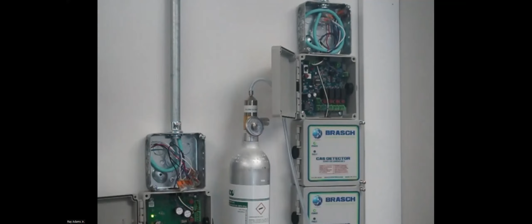And then you simply have to daisy chain that expansion pack right into the sensor that's closest to it on that particular floor. So instead of running your fans from the 5th floor of a parking garage all the way back to a maintenance room where you have your control panel, you take that and mount it right next to it. And as you daisy chain that expansion pack in, there's actually a repeater or a booster built in, designed to cut down on any interference that you may have as you have thousands of feet of wire running within these facilities.